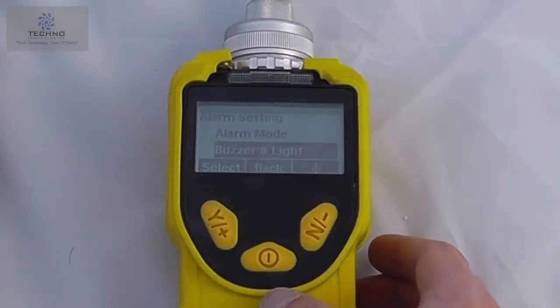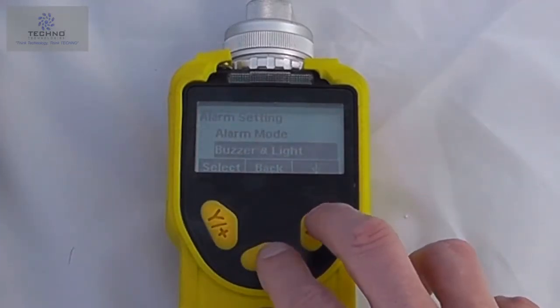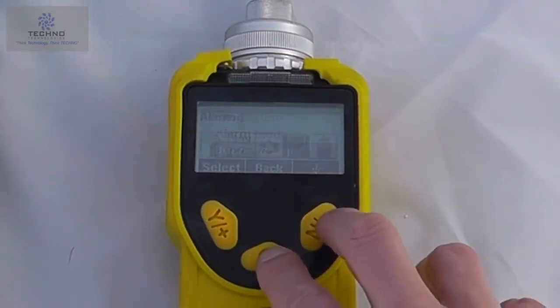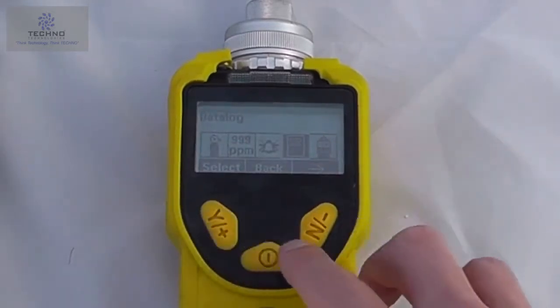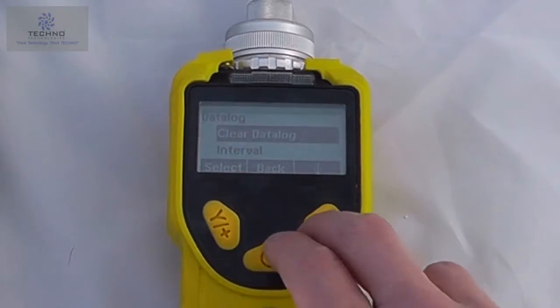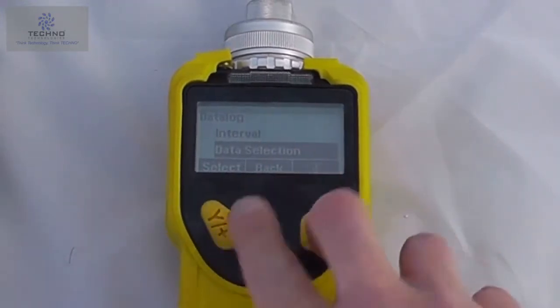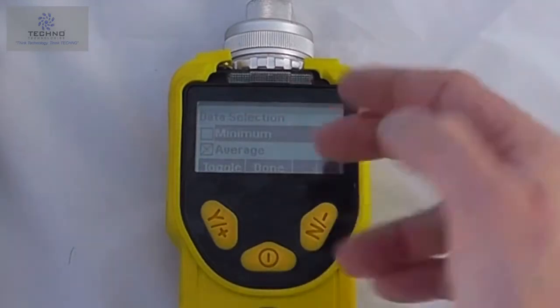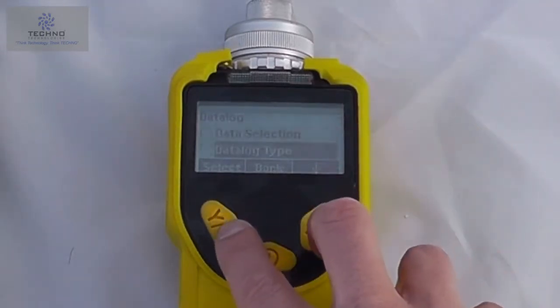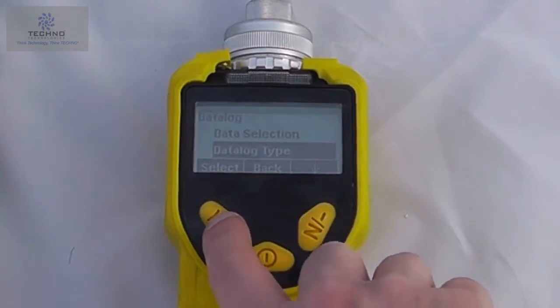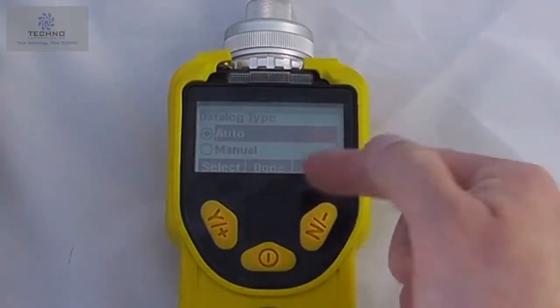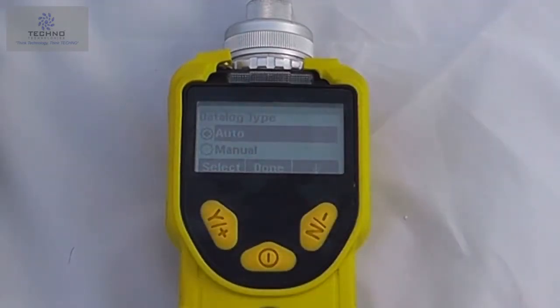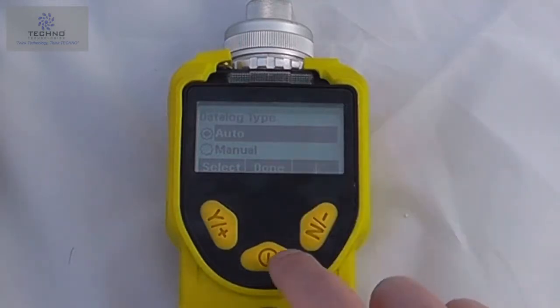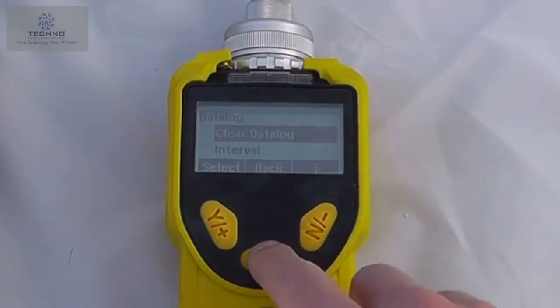Or I can look at the buzzer and the light settings, so whether we have a buzzer on its own or a light on its own. In our data log settings, we can change things like clear the data log or change the interval period. Look at the data selection, so what sort of things we want to log, be it minimum, averages, etc., STELs, TWAs. Our data log type, be it an automatic or a manual. So an automatic means it's data logging from startup, and manual means we select calibrate to data log. And then we're back to where we started.